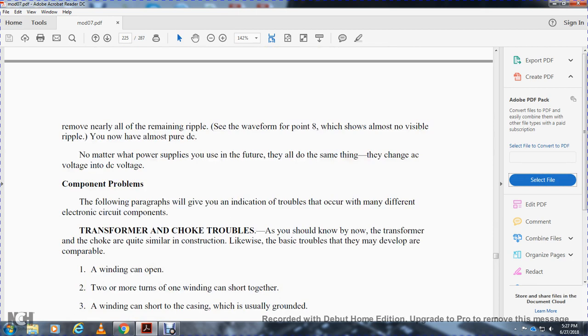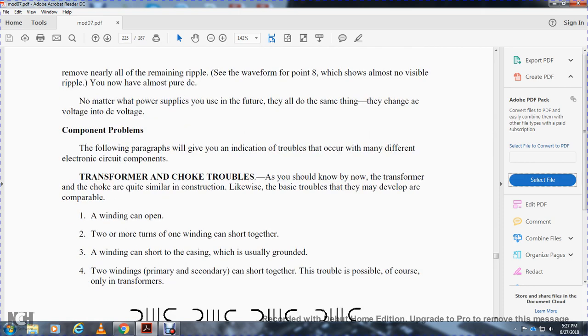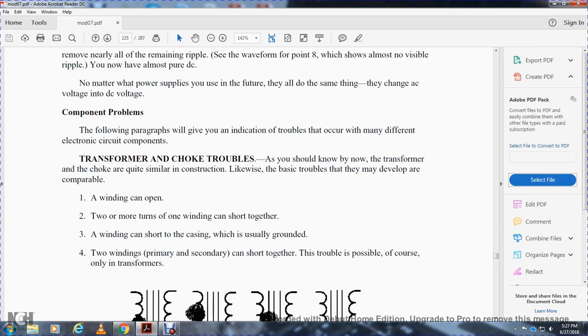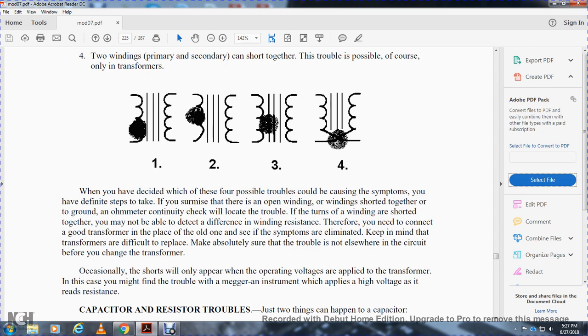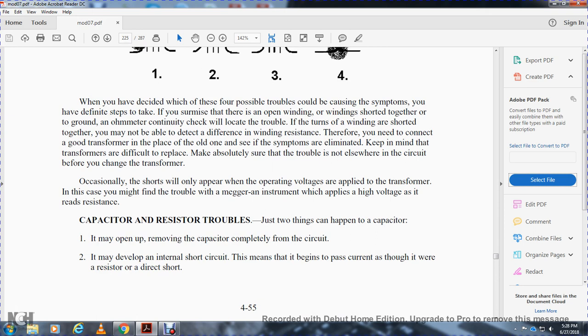The following paragraphs give an indication of troubles that occur with various electronic components. Transformers and chokes are similar in construction, and the basic troubles they develop are comparable. A winding can open; two or more turns of one winding can short together; a winding can short to the casing, creating a ground; and in a transformer, the two windings — primary and secondary — can short together. When determining which of these four possible troubles exists, you should take definite steps. An ohmmeter check will locate an open winding. If turns are shorted together, you may not detect the difference in winding resistance, so connect a known good transformer in place of the old one.